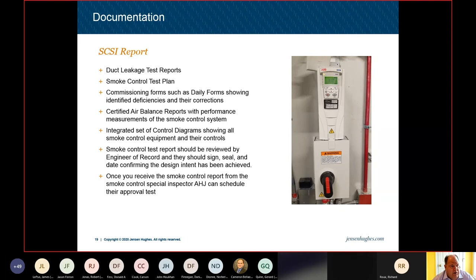Those are things the VFD gets monitored by the smoke control system, which, like I said, most of the time is the fire alarm system. So there are different things that we want to monitor, such as power, turning that unit off, and disconnects.